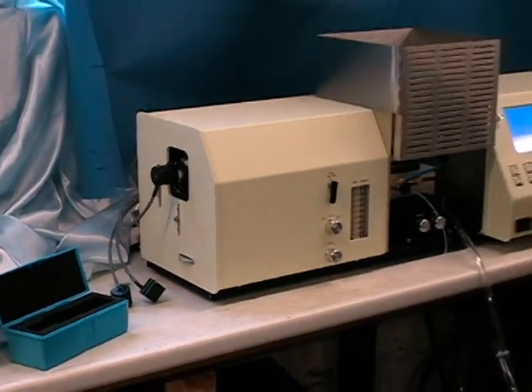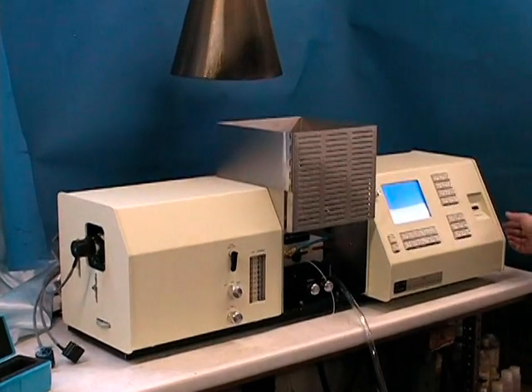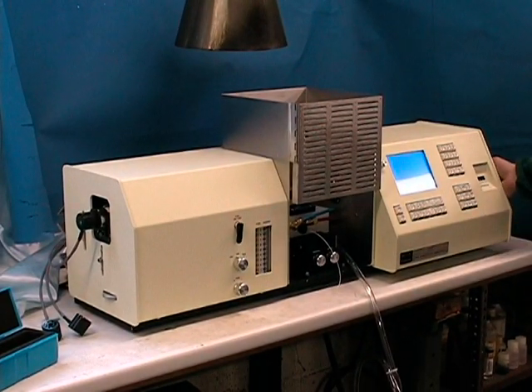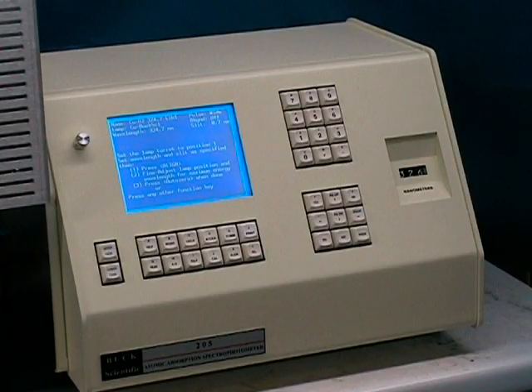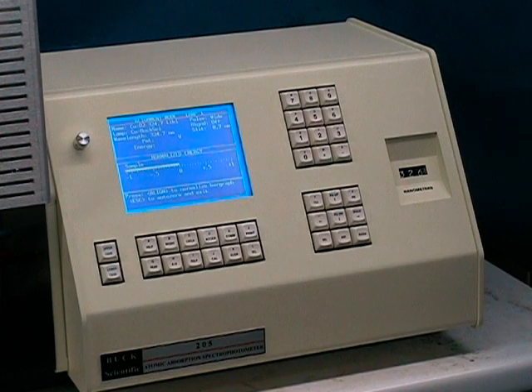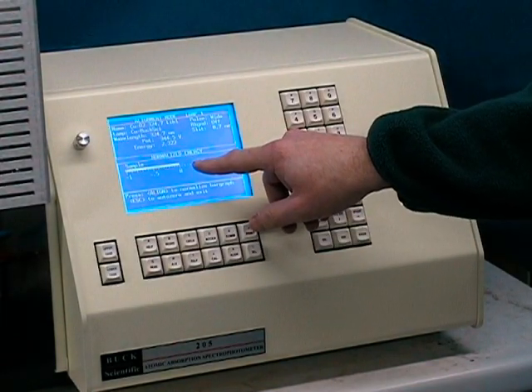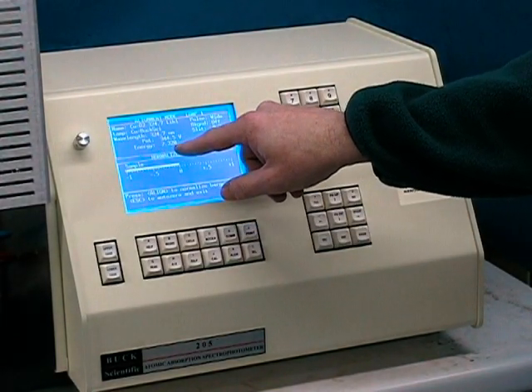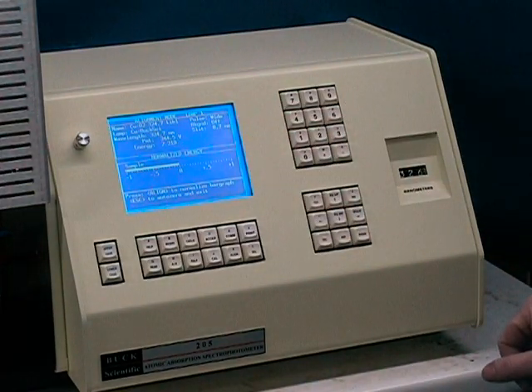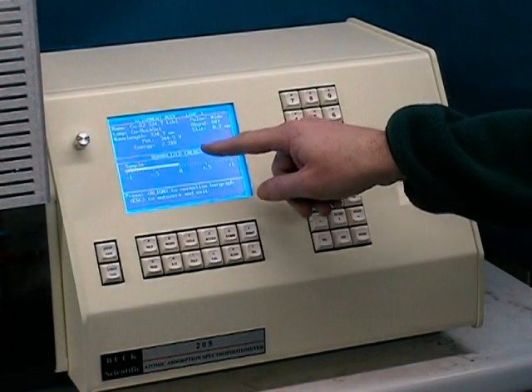Press the Align key and begin to optimize the energy of the hollow cathode lamp by fine-tuning the wavelength and looking at the bar graph signal or the energy number reading to maximize this energy. Once you have the correct hollow cathode lamp inserted into the proper lamp socket, we can now press the Align button, which will show us a bar graph of the energy based on the wavelength setting. Please be aware that the bar graph and the energy number above it represent the same thing, and you can set it either by the maximum energy number or the maximum position of the bar graph.